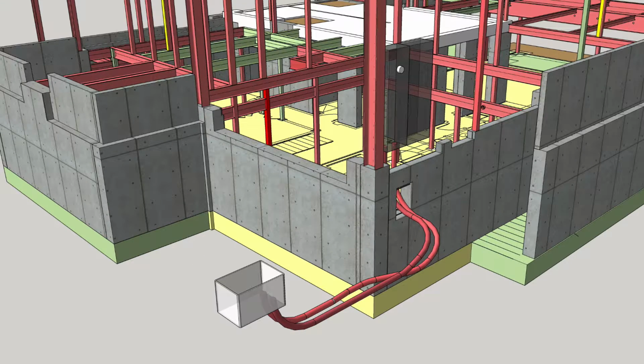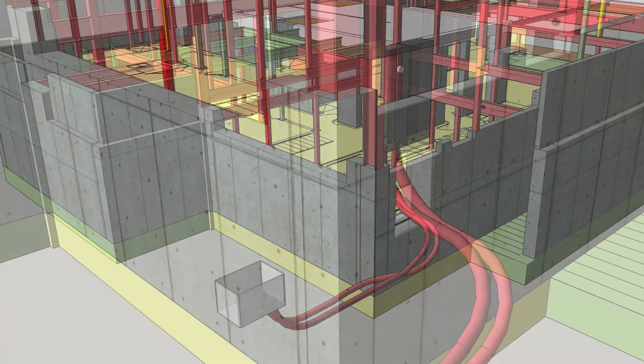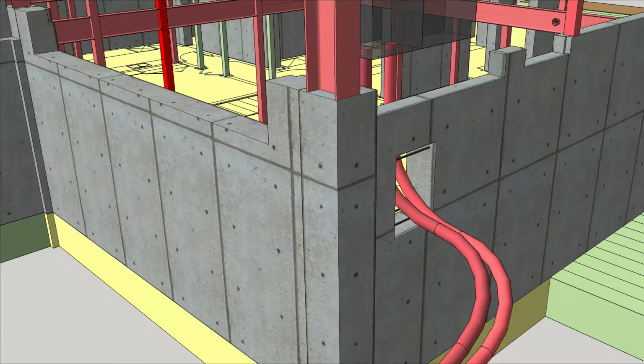This final pathway satisfied both the utility and the structural engineer. As we pull in closer to the model, notice the steep angle of the conduit sweeps where they pass through the retaining wall. There is no way to core through this wall after the fact that would allow for the sweeps to be passed through the wall.